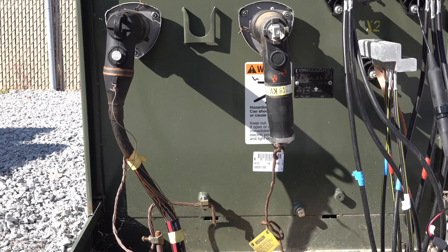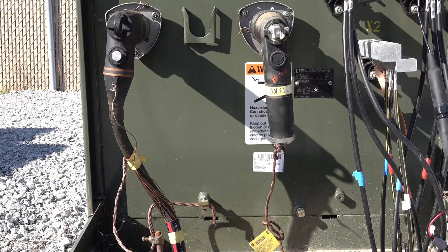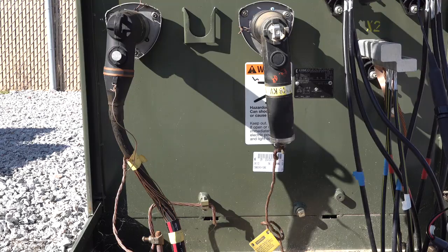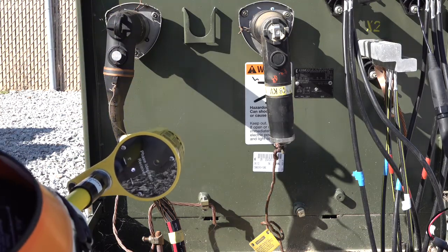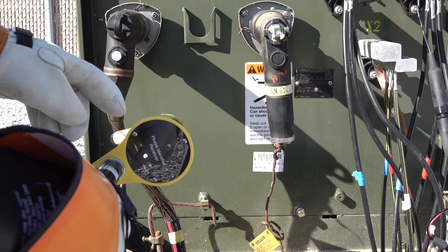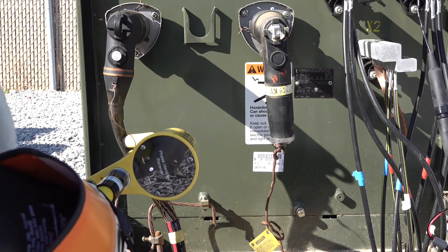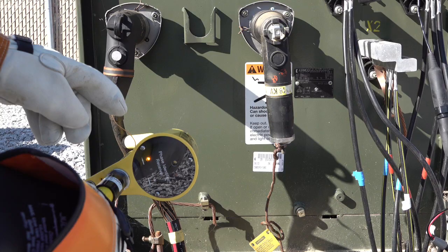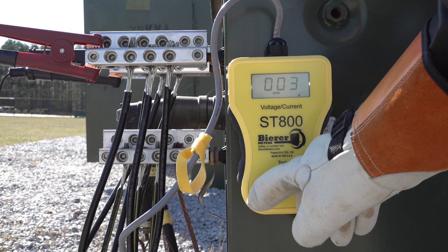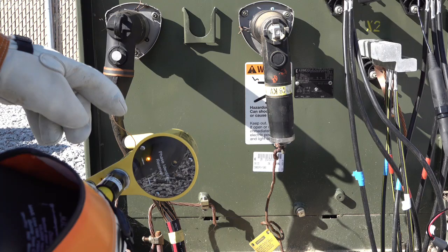But for demonstration purposes, the result would be the same if another single-phase pad mount were in series with this one. Again, with the red lead and the black lead both connected to the hot secondary bushings of the pad mount, we should get an indication only on the primary cable feeding this pad mount. Notice how the LED in relation to the arrow pointing up is on. If you recall, we have the black lead from the ST800 attached to the X1 bushing. Therefore, whenever we check the primary side, the arrow is going to be pointing up back into the transformer.